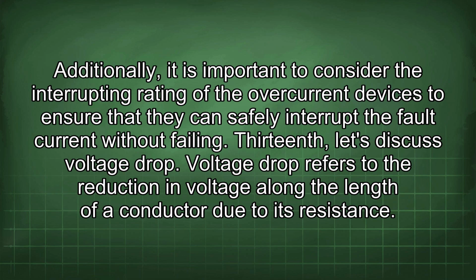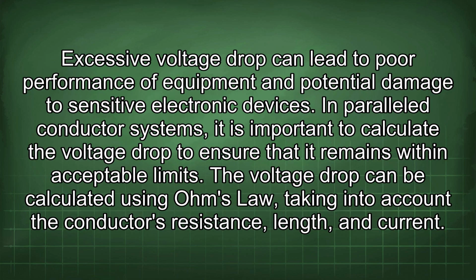13th, let's discuss voltage drop. Voltage drop refers to the reduction in voltage along the length of a conductor due to its resistance. Excessive voltage drop can lead to poor performance of equipment and potential damage to sensitive electronic devices. In parallel conductor systems, it is important to calculate the voltage drop to ensure that it remains within acceptable limits.